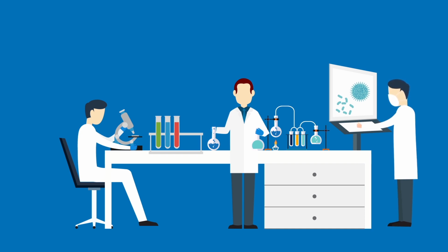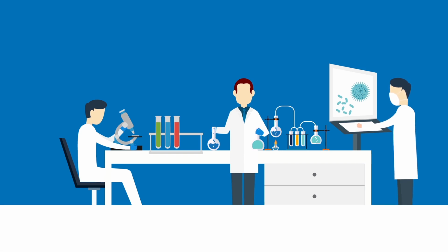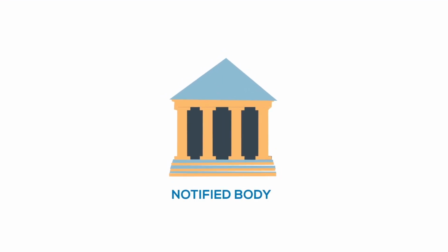In order to market a medical device in the EU, the legal manufacturer is obliged to engage with a notified body. Notified bodies are private organisations which are tasked with governing compliance with medical device regulations in Europe, and, as such, they determine when a device is in compliance with the regulations or not.